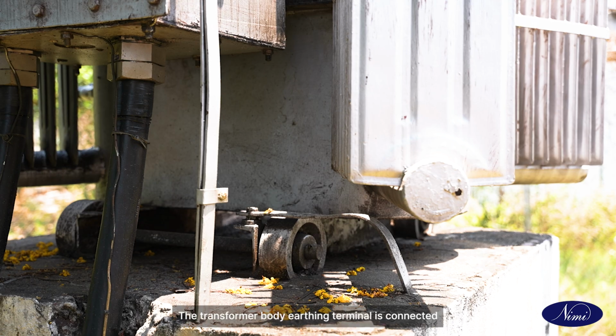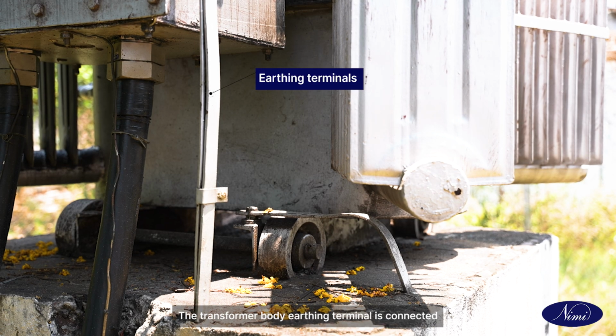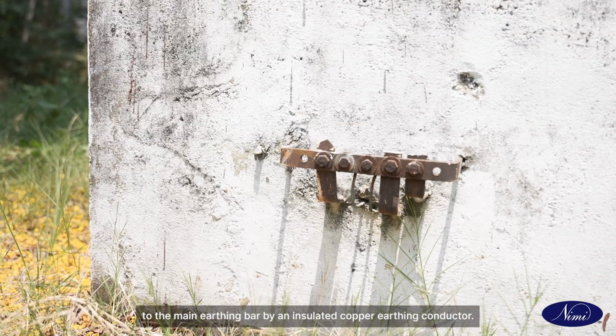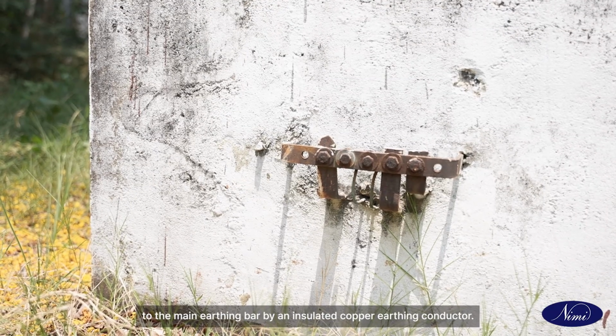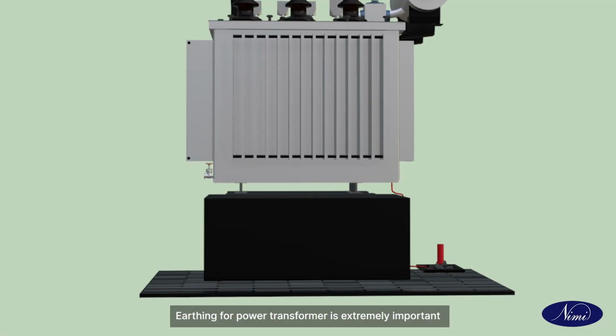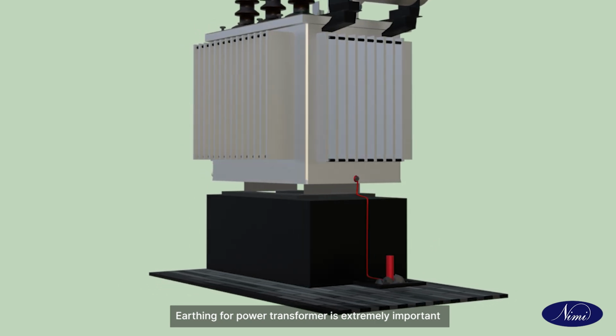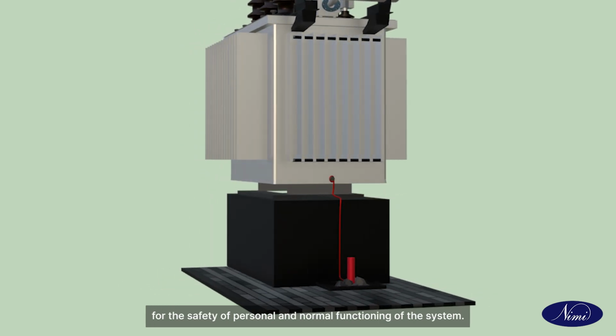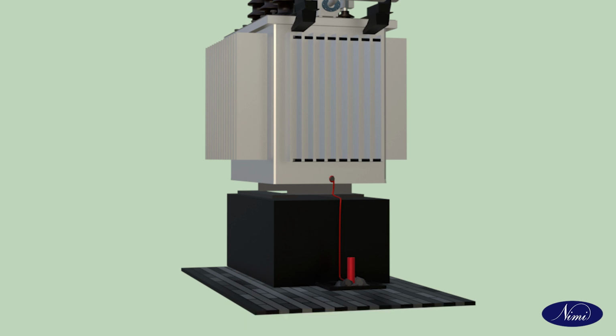The transformer body earthing terminal is connected to the main earthing bar by an insulated copper earthing conductor. Earthing for a power transformer is extremely important for the safety of personnel and normal functioning of the system.